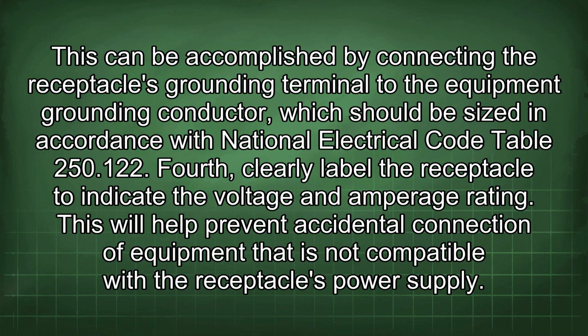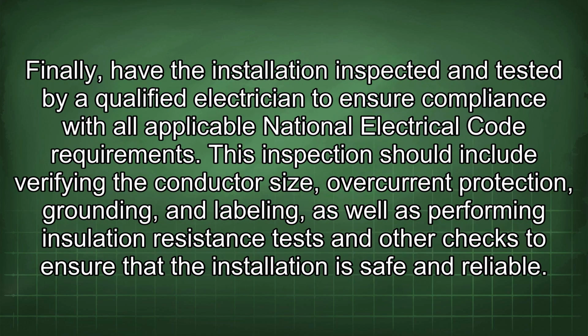Fourth, clearly label the receptacle to indicate the voltage and amperage rating. This will help prevent accidental connection of equipment that is not compatible with the receptacle's power supply. Finally, have the installation inspected and tested by a qualified electrician to ensure compliance with all applicable National Electrical Code requirements. This inspection should include verifying the conductor size, overcurrent protection, grounding, and labeling, as well as performing insulation resistance tests and other checks to ensure that the installation is safe and reliable.